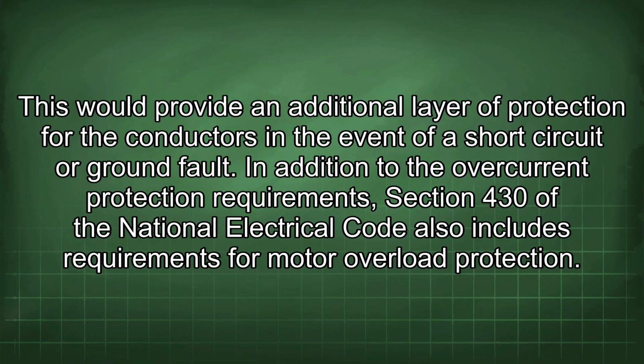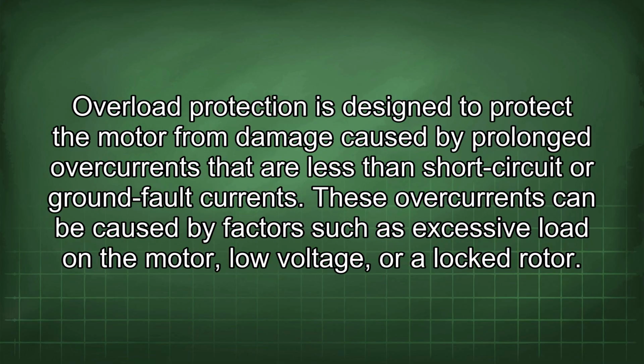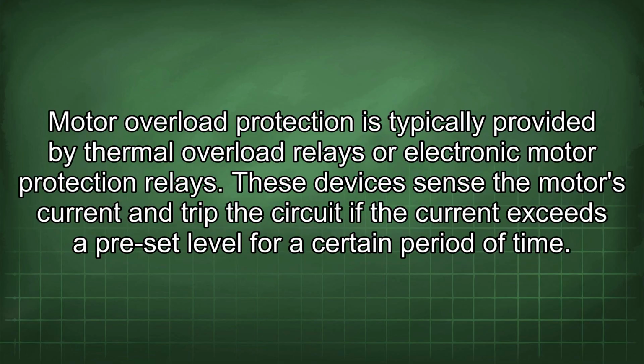In addition to the overcurrent protection requirements, Section 430 of the National Electrical Code also includes requirements for motor overload protection. Overload protection is designed to protect the motor from damage caused by prolonged overcurrents that are less than short circuit or ground fault currents. These overcurrents can be caused by factors such as excessive load on the motor, low voltage, or a locked rotor. Motor overload protection is typically provided by thermal overload relays or electronic motor protection relays.